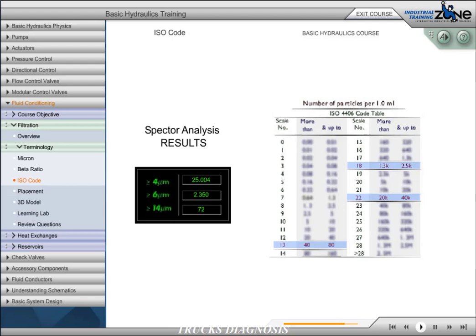This ISO code is meaningful only if we can relate it to the required cleanliness level of our hydraulic system. This is usually based on a manufacturer's requirement for cleanliness levels in which a component may operate. For example, most servo valves require an ISO code of 15, 13, 12 or better, while gear pumps may operate adequately in fluids with an ISO code of 18, 16, 15.